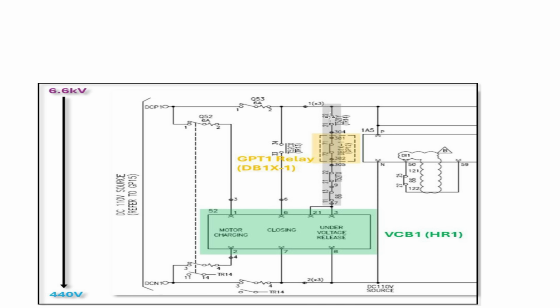If all of these relays don't stay closed, the voltage from here will not make it into the under voltage release relay. All of this right here will just go to zero, and that's what triggers the HR1 to fail. So we know that failure was here, and that's how they narrowed it down.